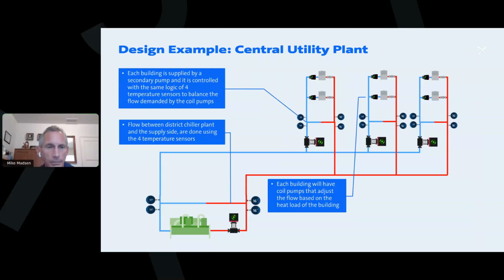Here's another one. We do a lot of process cooling. Have you seen these successful in industrial facilities where chill water is feeding various cooling needs, not necessarily air handlers? Yeah, it can work the same. We're just starting to branch out. Our industry team is just starting to promote distributed pumping. There's a lot of interest. I mean, data centers, some people call it industry, some people don't. But yes, we could do this with process cooling as well. Anywhere where they're using these control valves to control the flow, we could look at replacing the control valve with a smart pump.